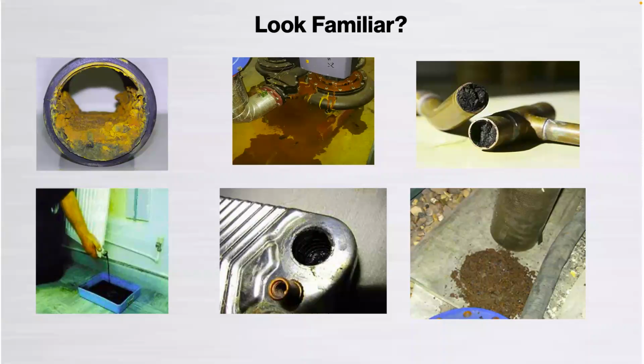And then finally, the picture to the right-hand side is actually really good to see. You may not think that, kind of counterintuitive, but that's a flushing project in London in the UK, whereby all the terminal units were in bypass. So they had flushing bypasses at the terminal units. Any sensitive equipment was bypassed before any pump was turned on. The pumps were then turned on.